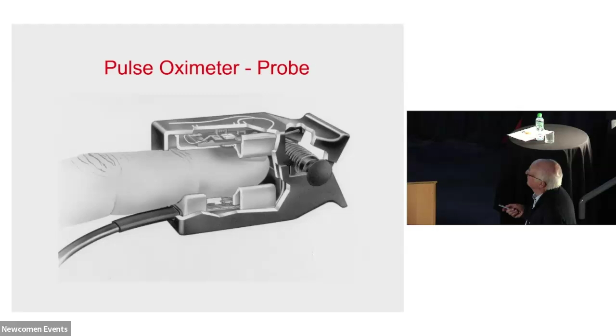But he made it work by looking at 660, which is red, and 940, which is in the near infrared. One of the snags is that there were no light-emitting diodes available near the isobestic point. There is now. There's one at 807, a light-emitting diode. But the advantage of the light-emitting diode is it can be switched very rapidly indeed. So what you had was the one finger probe, which you must all have had applied to you at some time, which had a photodetector on one side and two light-emitting diodes on the other side.